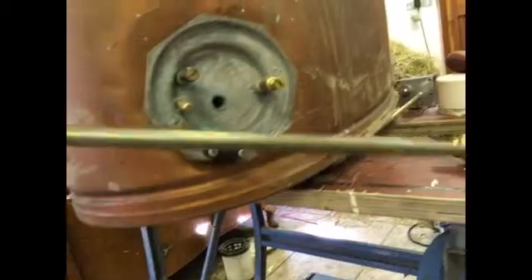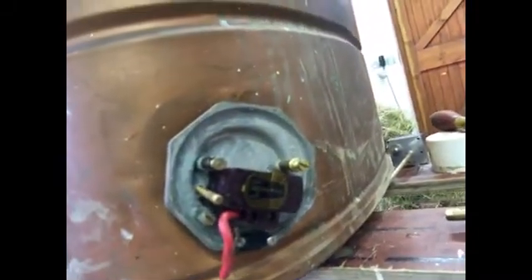Here's the other type - a very old one. The only real difference is the same look; you take the stat out of its pocket and it looks identical, you could swap one to the other. The element is connected by two simple screws, one each side. This old one doesn't have an overheat protection - those aren't allowed anymore, but they do last quite well.